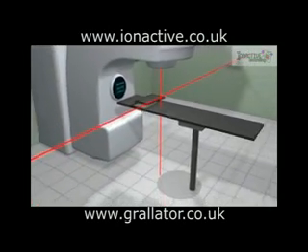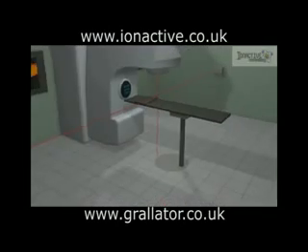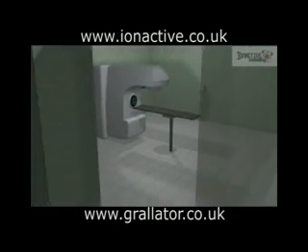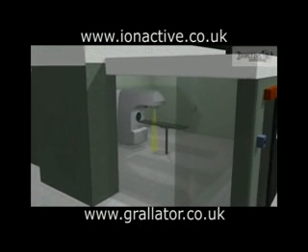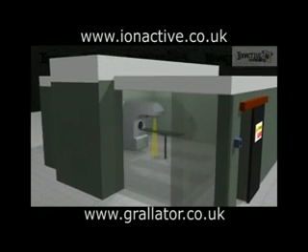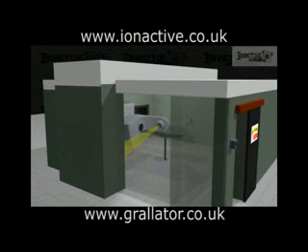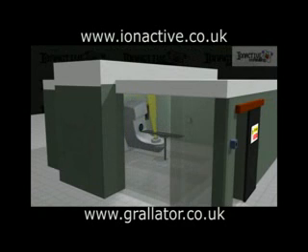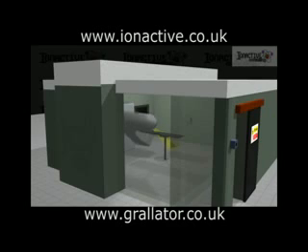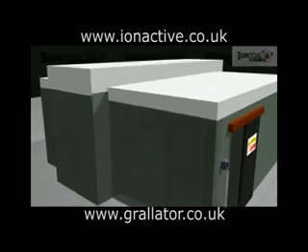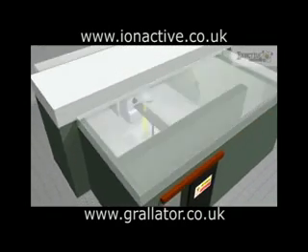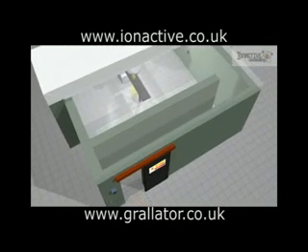The LINAC is usually situated within a specially designed room so that staff and public doses from its operation are minimised. The room will have a thick primary concrete shield to absorb direct beam radiation and thinner secondary concrete shielded walls to absorb scattered radiation. In addition, the access to the room will typically be through a maze geometry so that the doorway does not have to act as a full secondary shield.